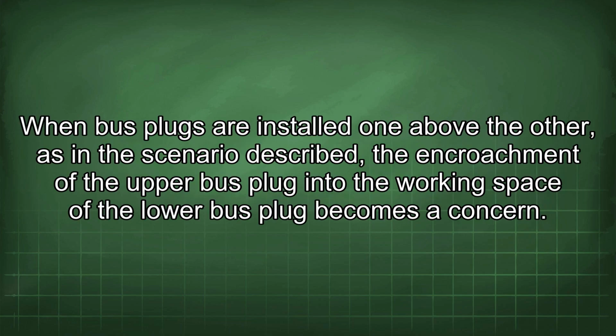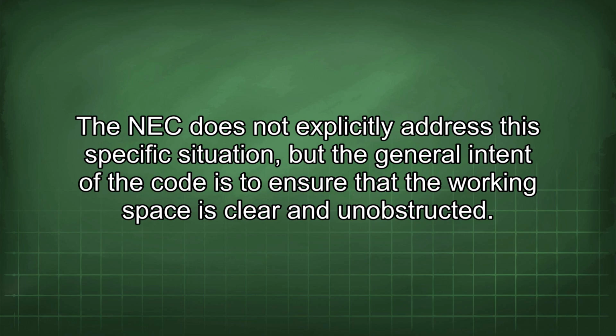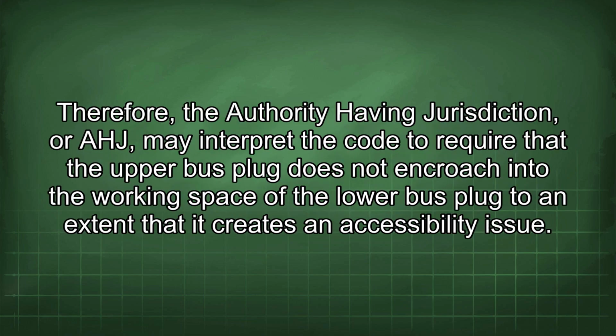When bus plugs are installed one above the other, as in the scenario described, the encroachment of the upper bus plug into the working space of the lower bus plug becomes a concern. The NEC does not explicitly address the specific situation, but the general intent of the code is to ensure that the working space is clear and unobstructed. Therefore, the authority having jurisdiction, or AHJ, may interpret the code to require that the upper bus plug does not encroach into the working space of the lower bus plug to an extent that it creates an accessibility issue.